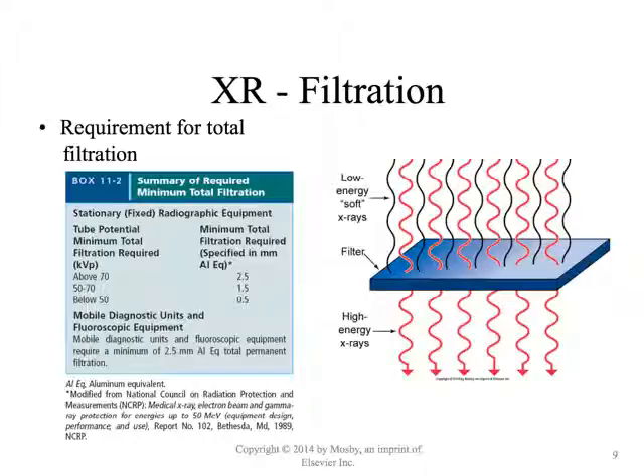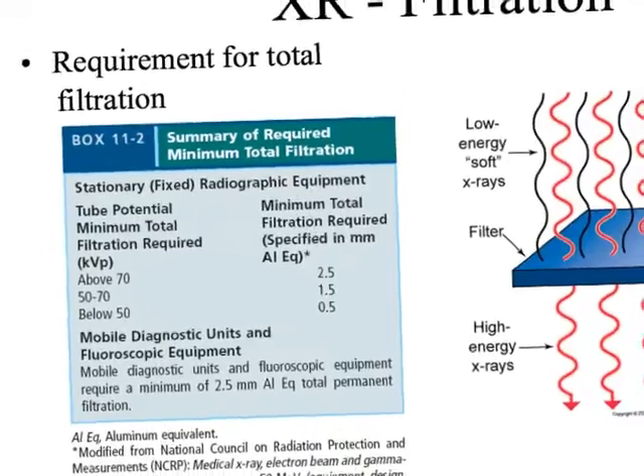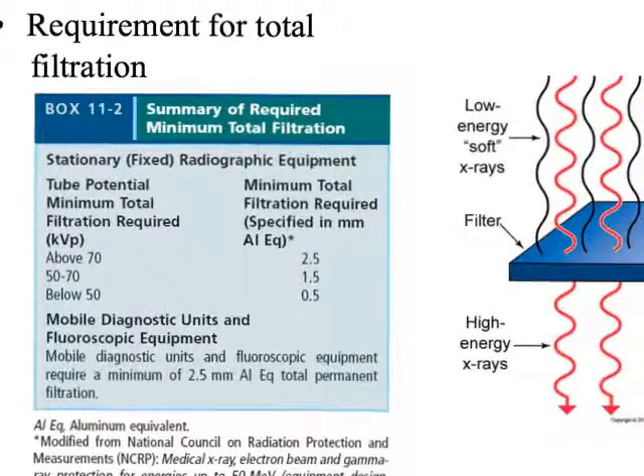Related to that is filtration. Filtration is some amount of aluminum equivalent, and we can see it's tied directly to the amount of energy of that X-ray beam. So I'm going to zoom in here a little bit. In general, we're talking about 2.5 millimeter aluminum equivalent filtration for pretty much every diagnostic X-ray machine you will ever work on. That's total filtration, so inherent plus added filtration. Inherent filtration would be the filtration inherent in the machine, in the tube itself, plus some kind of added filtration. You don't sit there and add the filtration yourself. The X-ray tube is constructed that way.